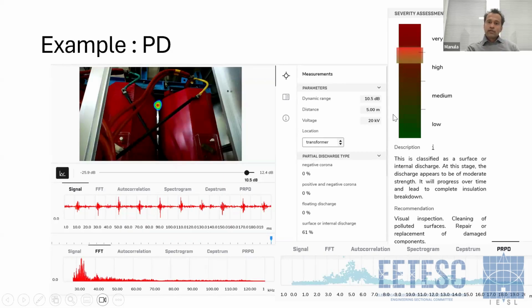So for example, they can input the voltage level and the location, so that these tools give automatic recommendations, and it gives a description. In this case, it says that this is classified as a surface or internal discharge. At this stage, the discharge appears to be of moderate strength. It will progress over time and lead to complete insulation breakdown.